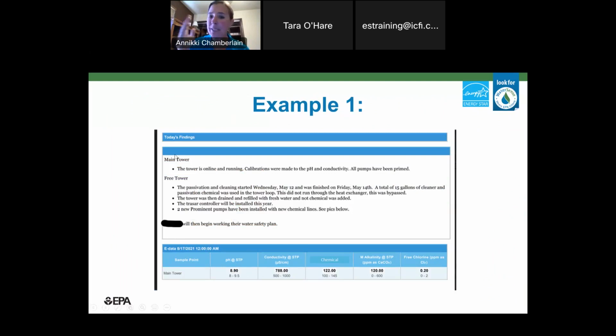Here's a good example. So in example 1, we can see that we have some notes on the tower. That's good, good notes about what's going on, but really, what do I see as far as chemistry? I see basically the chemistry of the tower, but I don't know what the chemistry coming in is. So I'm kind of flying blind here as a property manager or an auditor or whatever my role is. So really, what we would want to do is have this person include what the makeup water coming into the tower was. Like, this tower is softened. So right now I have no idea what cycles they're running at, but that's going to be important to me because that's the service I'm paying for.